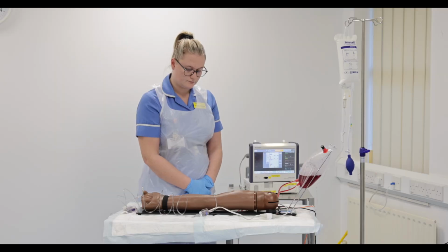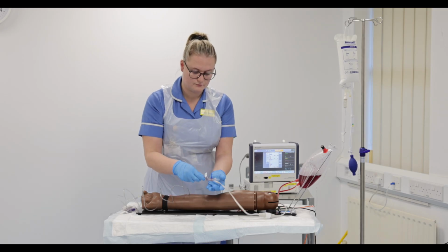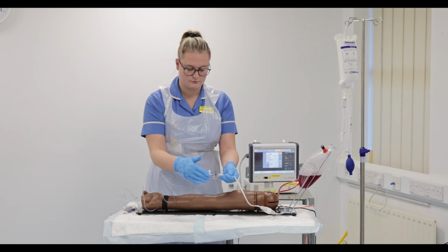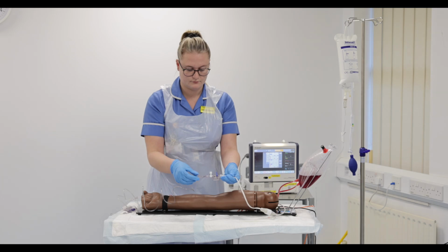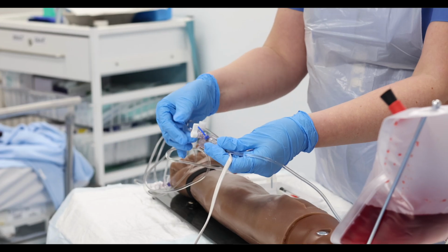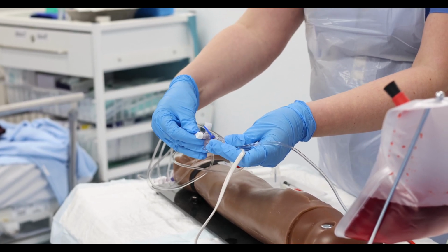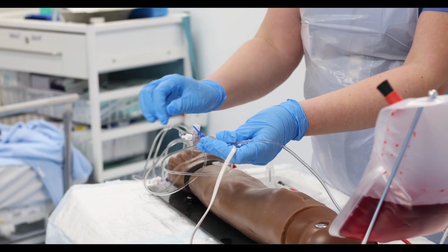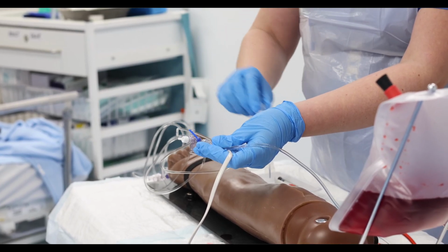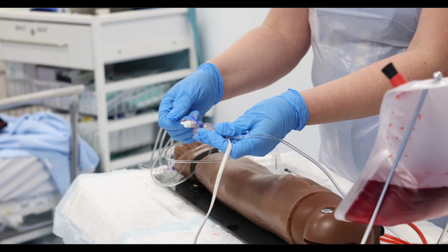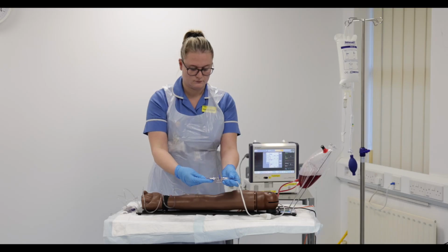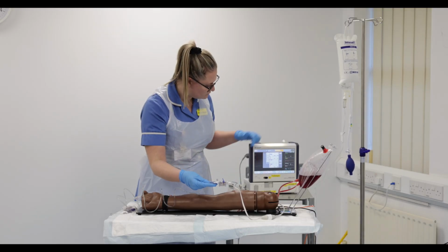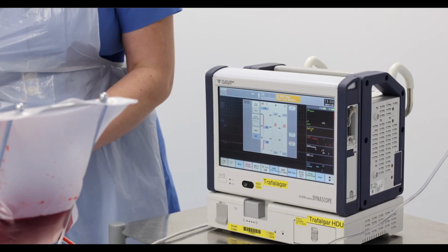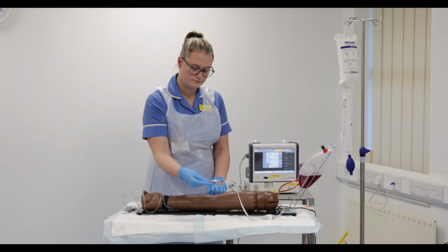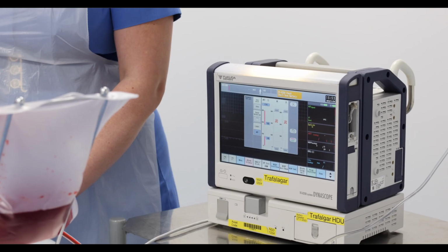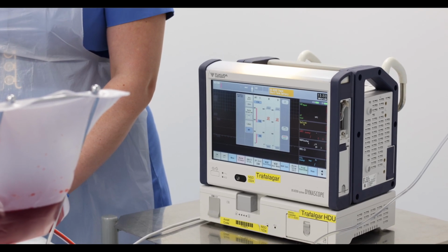Going back to your arterial line, ensure that the transducer is placed in line with the heart for accuracy. Open the port to air by turning the stopcock away from the patient and remove the temporary bung, keeping the transducer in line with the heart. Going back to the monitor, you can now press 0. To confirm that the line has now been zeroed, you should see on the monitor that it says 0 confirmed.